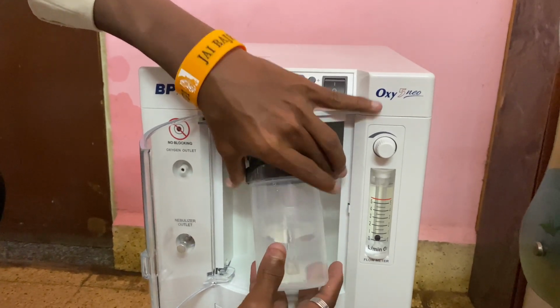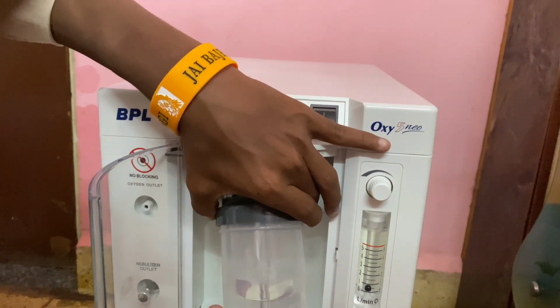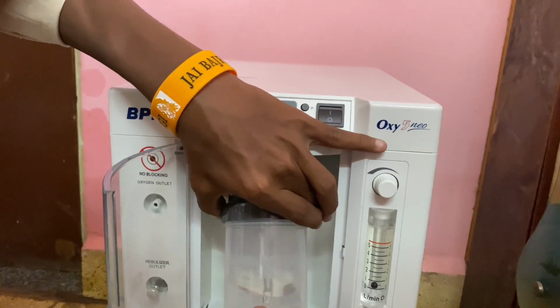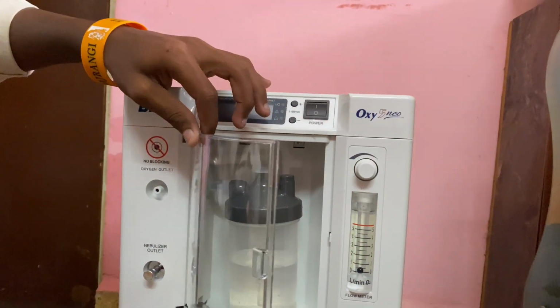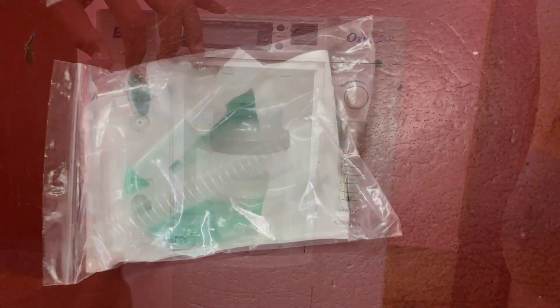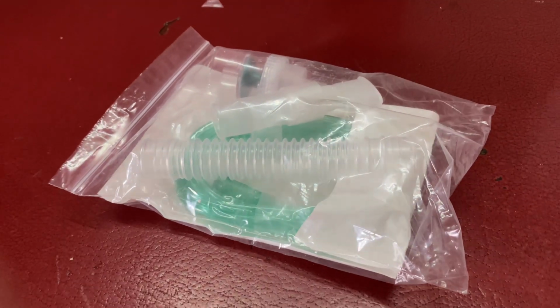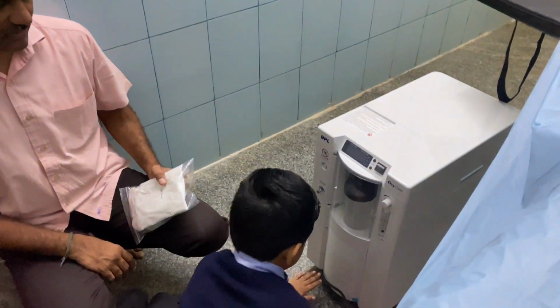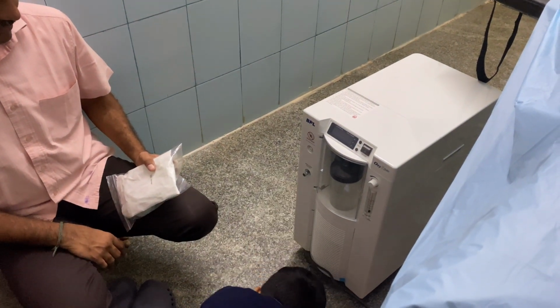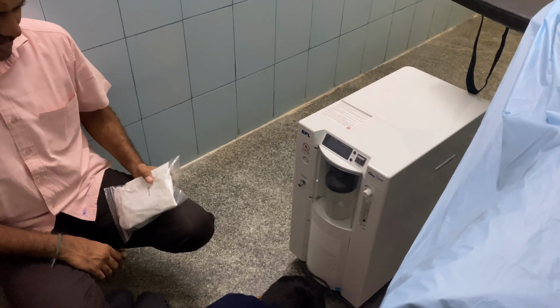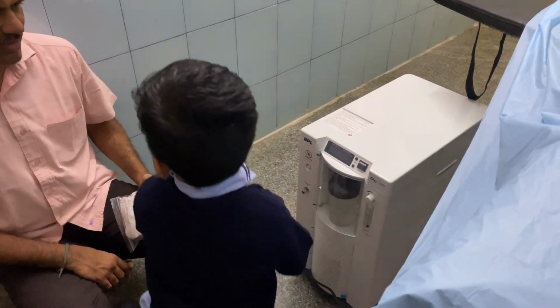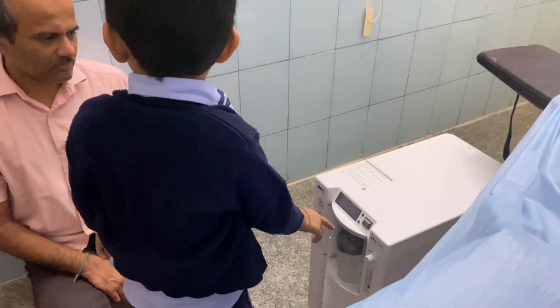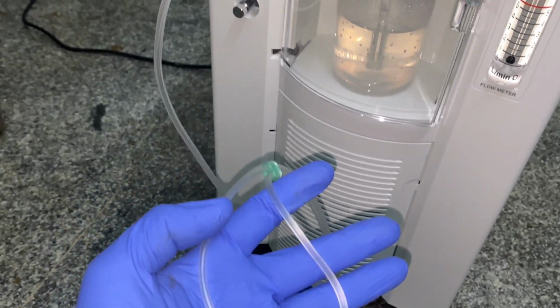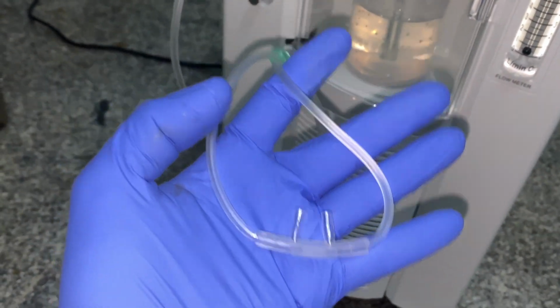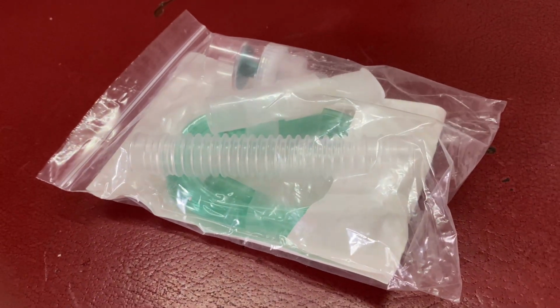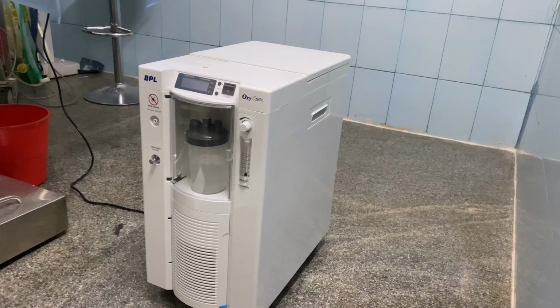Here, we get a maximum and minimum level to add the water. If we don't get distilled water, then we can put RO water also. Here, we are facing some issue in the closing of the humidifier chamber. We get a nasal probe as well as a nebulization kit along with this.